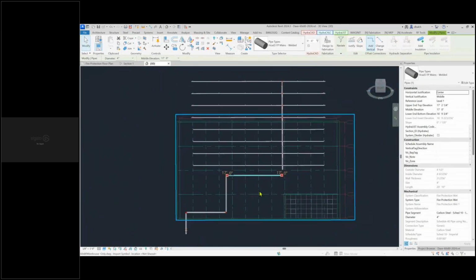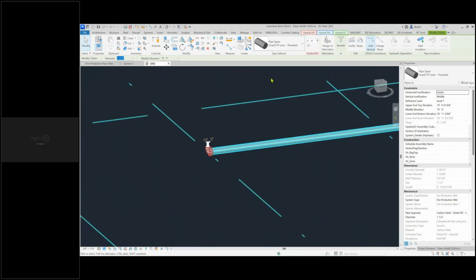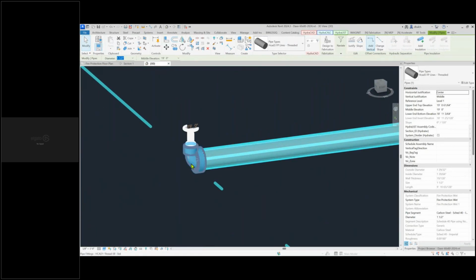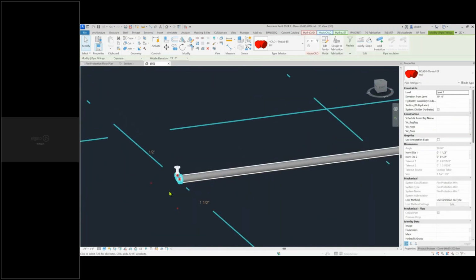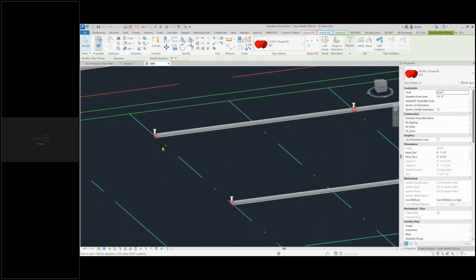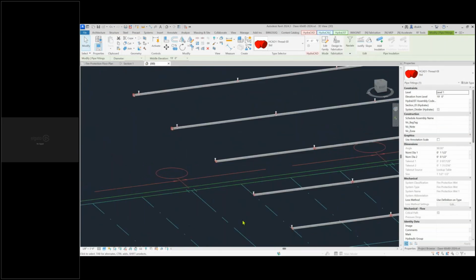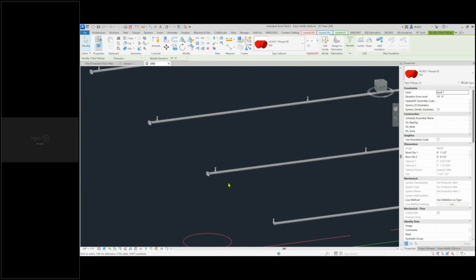And Dave, if you zoom in on the end of one of those threaded branch lines, do you see the elbow that connects the 1.5-inch pipe to the 1/2-inch sprinkler outlet? They make threaded fittings like that. They make a 1.5-inch by half threaded elbow, but the welded outlets are 1/2-inch threaded things that need to get cut into and welded onto the piece of pipe. So we need to run the pipe past in order to weld that outlet on, and then we cap the open end with a cap.